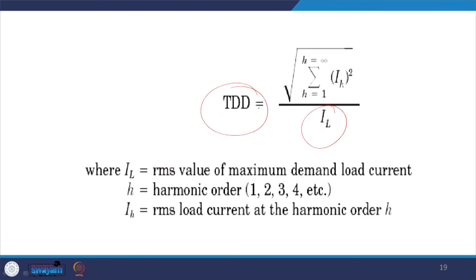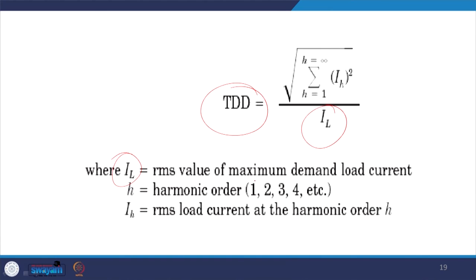TDD is basically the harmonic current divided by the demanded load current. If you are not drawing the full load current and your harmonic content is high, you cannot penalize the utility. But when you are drawing the full load current, the measurement is taken at full load. Il equals the RMS value of the maximum demand load current, and Ih is the RMS of the harmonic current excluding the fundamental.